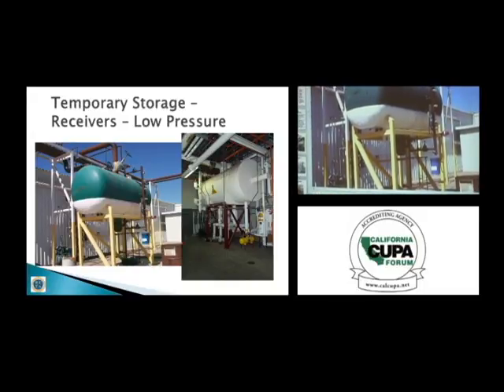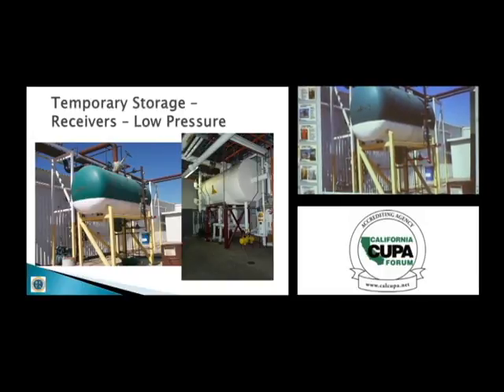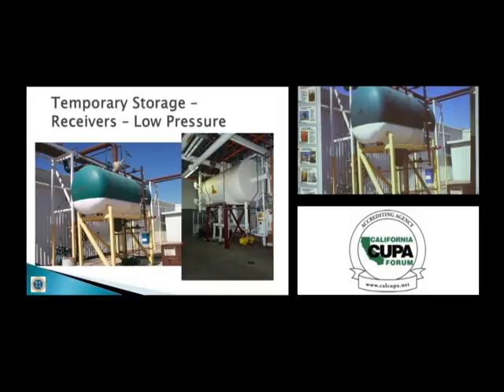You can even go into the technical side. You got a globe valve here that the flow through a globe valve kind of has to take a course like that. And so you end up with a dam, the outlet is holding back what's on the inlet side. But if they had just rolled that thing over so that the path was horizontal through, things like oil going to this is what you're counting on for your instrumentation. Now, please don't go out and tell everybody you got to roll your valves over. But when they're installed, comment, hey, that one is turned to the side. I just learned that that's a good idea. Good for you.